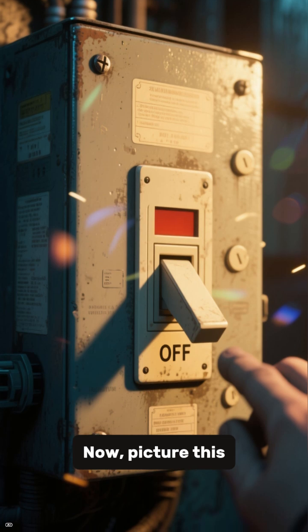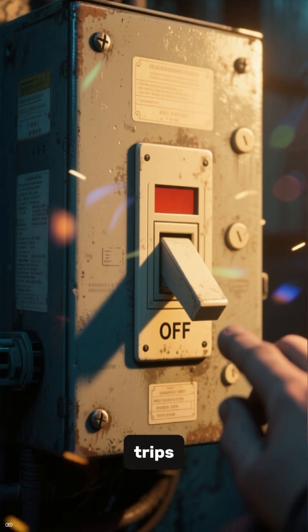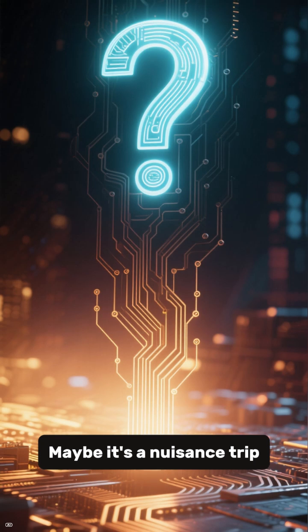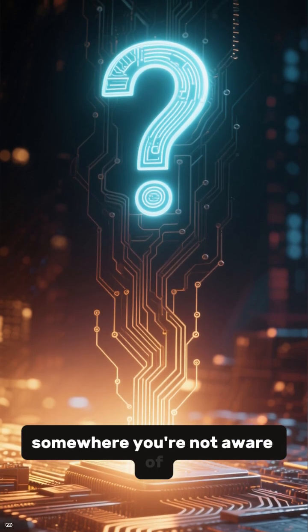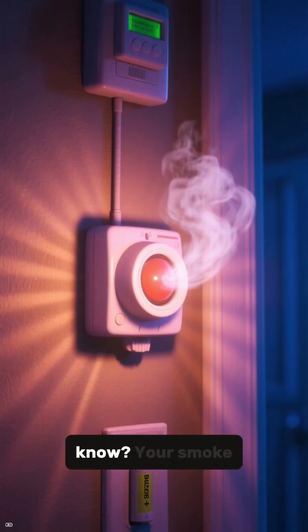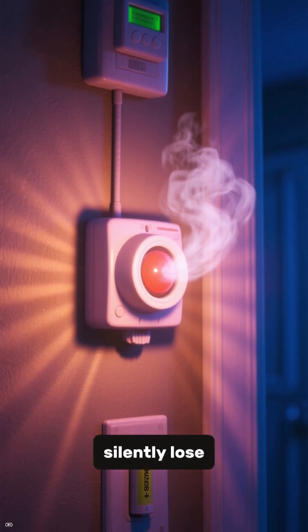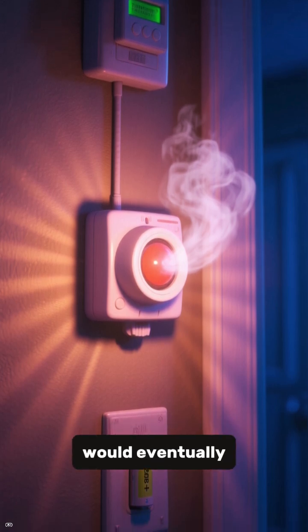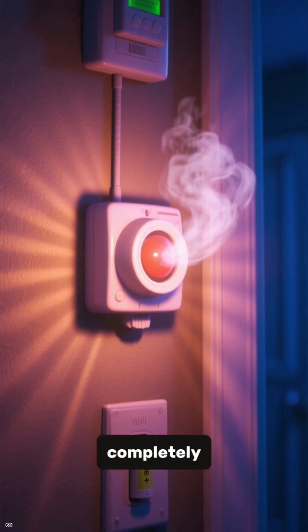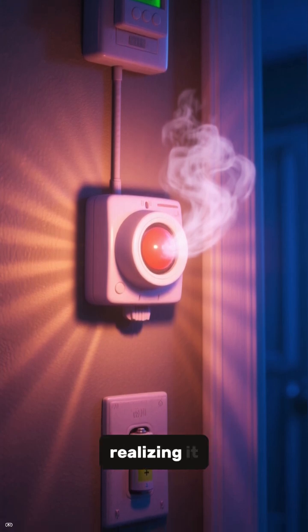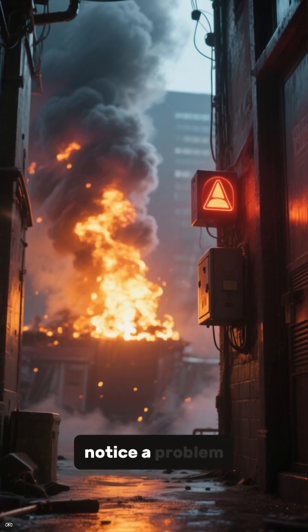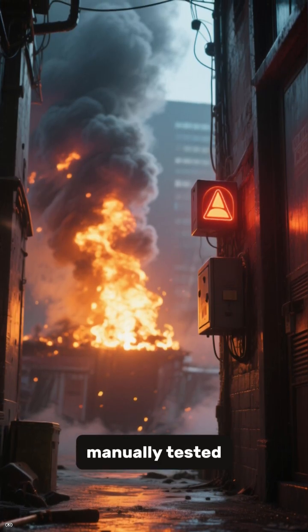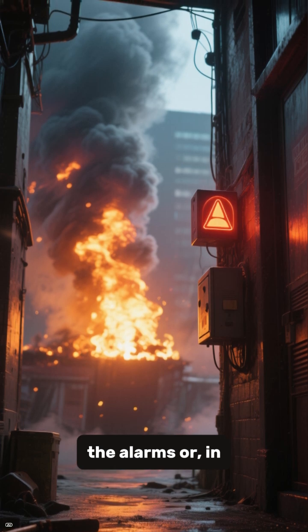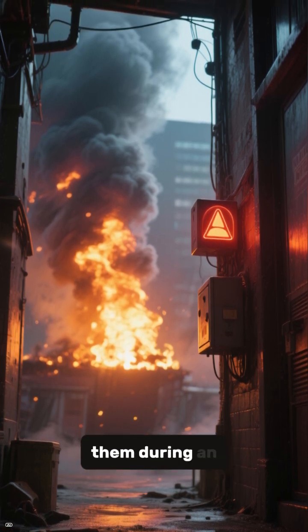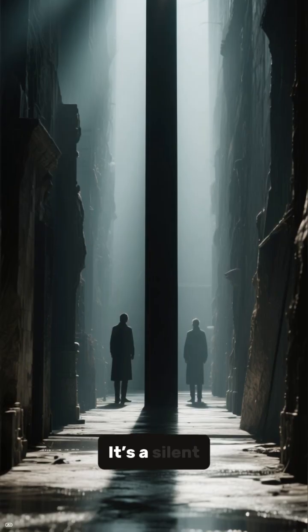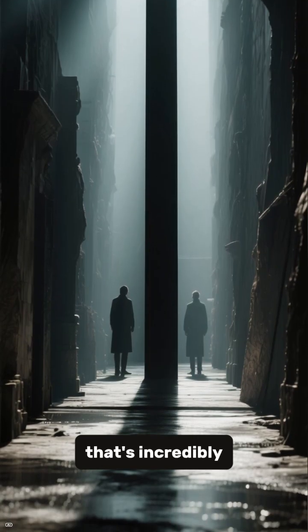Now, picture this. The breaker for that circuit trips. Maybe it's a nuisance trip. Maybe there's a small fault somewhere you're not aware of. How would you know? Your smoke alarms would silently lose power. Their backup batteries would eventually drain, and you'd be left completely unprotected without even realizing it. You wouldn't notice a problem until you either manually tested the alarms or, in the worst-case scenario, needed them during an actual fire. It's a silent failure, and that's incredibly dangerous.